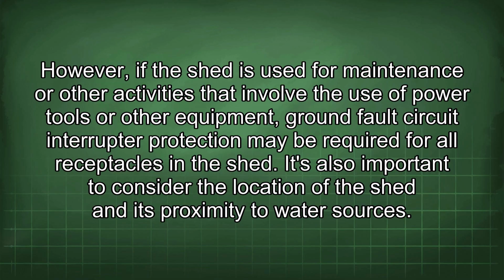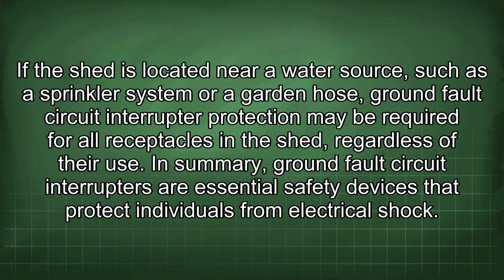It's also important to consider the location of the shed and its proximity to water sources. If the shed is located near a water source, such as a sprinkler system or a garden hose, ground fault circuit interrupter protection may be required for all receptacles in the shed, regardless of their use. In summary, ground fault circuit interrupters are essential safety devices that protect individuals from electrical shock.